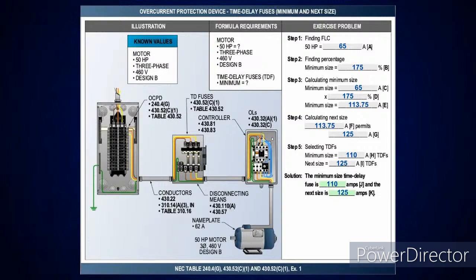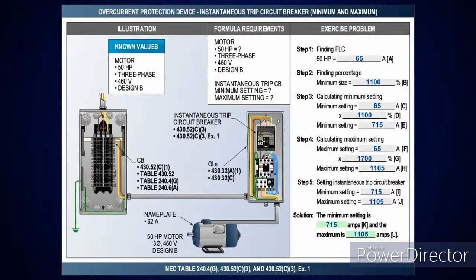Okay. Right. Now, when I come over here and I look at an instantaneous trip circuit breaker, you're going to look over at the table, and we have a design B energy efficient motor here. It's going to tell you take it at 1100%. Okay. Now, you take the 65 amps at 1100%, that's 715 amps. That's your minimum setting to start with. Right. Then if you go over and you pick up C3, it's going to allow you to go up to 1700%, and you'll pick up (C)(3)(2)(b).